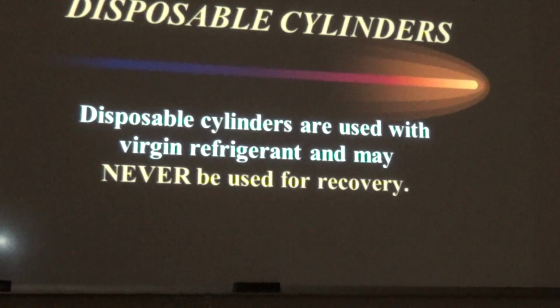The one tank we just talked about was the refillable tank. There are also disposable tanks. Those disposable tanks are where you buy the new refrigerant. They're a lighter weight tank, they're color coded, and they say on the side of them what kind of refrigerant goes in them. Like I said, they are used with factory fresh refrigerant. They're never used for recovery.